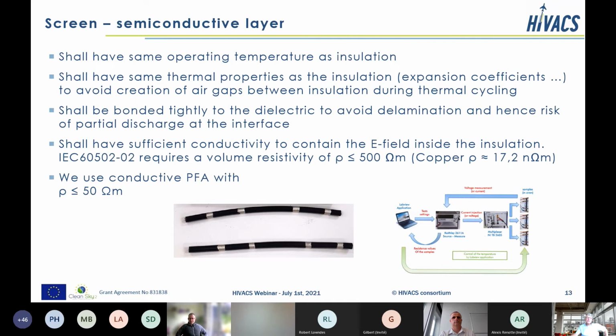Regarding the semiconductive layer, we have been using a semiconductive PFA, because then it has the same base material as the insulation PFA, so having the same thermal properties. So we avoid a delamination of the 3 layers during thermal cycling. And also the semiconductive layers shall be bonded tightly together to avoid any delamination. The semiconductive layer shall be sufficiently conductive to contain the electrical field inside the insulation.